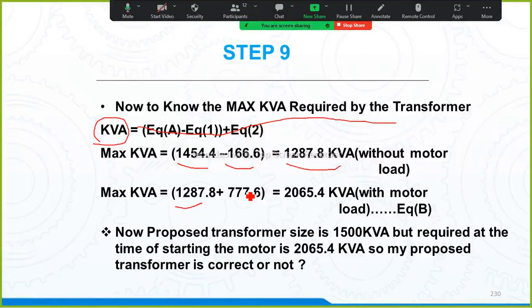Considering that 1287.8 plus 777.6, that is equal to 2065.4 kVA with motor load. इसका मतलब क्या है? अभी जब मोटर चालू हो रहा है, when the motor is switching on, the maximum kVA required by all together, the total load is how much? 2065.4 kVA. But how much time will it take? Only for the first 3 to 5 minutes, na?